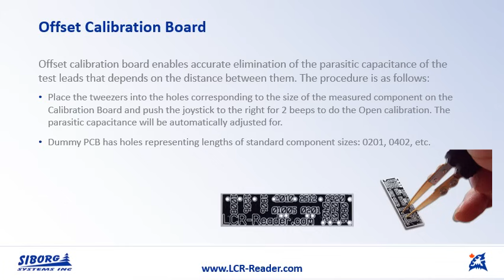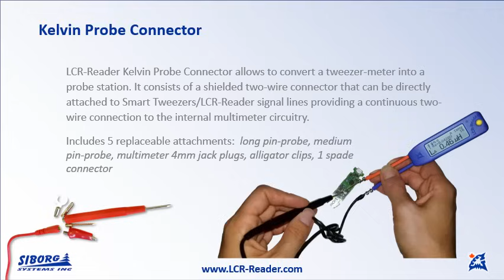It allows you to accurately eliminate the parasitic capacitance of the test leads, because it depends on the distance between them. You have to specify a specific distance, so that board has holes corresponding to the specific sizes of the components. Kelvin probe connector is a shielded 2-wire connector that connects perfectly onto the signal lines of the LCR reader or smart tweezers, and therefore it gives you rather low parasitics involved when you do the measurements. You could use it to measure impedances on any board, on any location of the board, or the waveforms if you use an oscilloscope function.